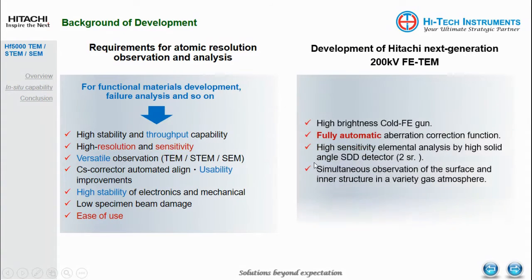So with these requirements, Hitachi has developed this next generation 200 kV field emission TEM or STEM. It comes with a high brightness cold-FE gun, which provides very high resolution and stability of the gun itself.